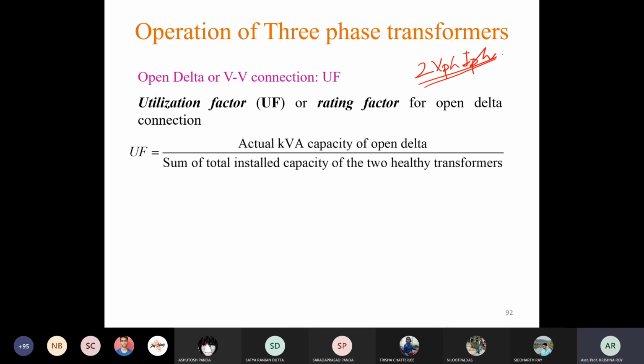So utilization factor is the actual kVA capacity of open delta divided by the total installed capacity of the two healthy transformers. This is obviously 2 V phase I phase, and the actual kVA capacity of open delta is √3 V phase I phase. So that is √3 by 2, which is 86.6%. We have installed 2 V phase I phase capacity, but we are able to use only 86.6% of the total installed capacity. So that is one kind of loss actually, one disadvantage of this open delta or VV connection.